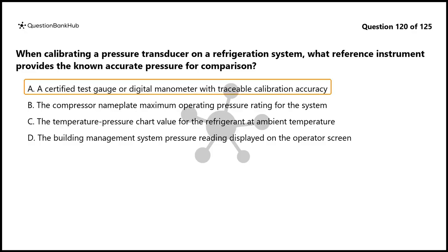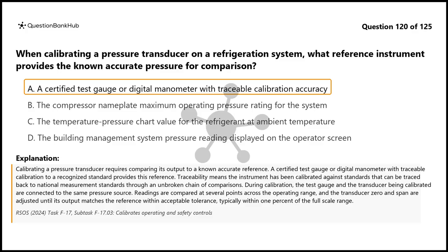The correct answer is A. Calibrating a pressure transducer requires comparing its output to a known accurate reference. A certified test gauge or digital manometer with traceable calibration to a recognized standard provides this reference. Traceability means the instrument has been calibrated against standards that can be traced back to national measurement standards through an unbroken chain of comparisons.